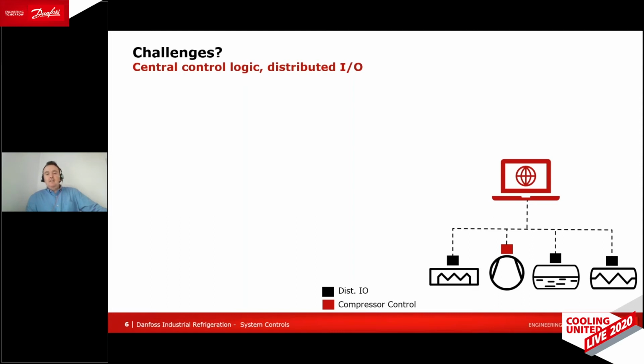But the tendency in Europe is to have these distributed I/O panels, and inside those you have all your connections—so all your evaporator, condenser, and vessel sensors and actuators. They'll be connected to the panel, where they get translated to a field bus signal and then pulled back to the main PLC.